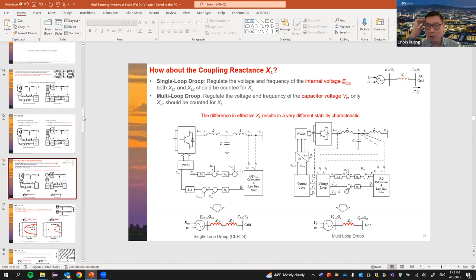So when you implement this droop control, you usually have a filter there, which is somehow equivalent to some inertia, but it's quite small. So do you think that we really need inertia, or should we use some large inertia constant for that grid forming control? That's a good point. When we design the droop control, the purpose of that low pass filter is to filter out those harmonics, right? When you measure the power P and Q, you don't want those harmonics to impact your control behavior. So that's the purpose of the low pass filter.